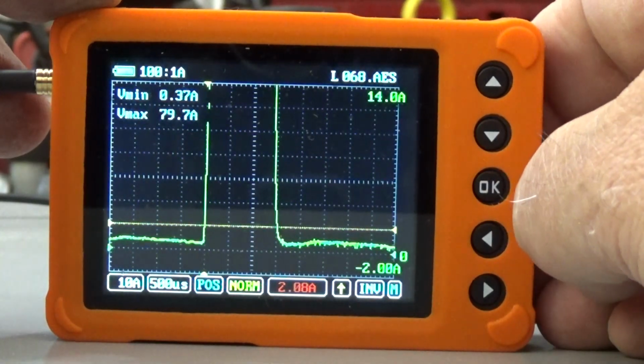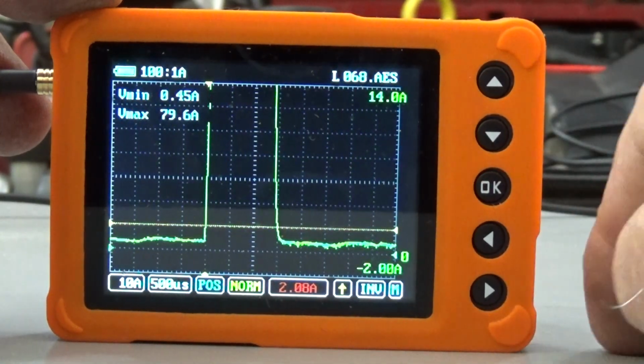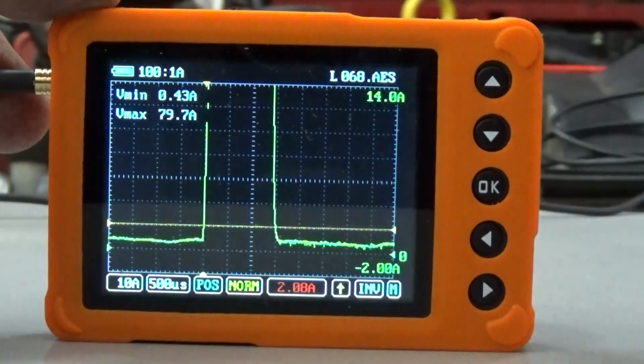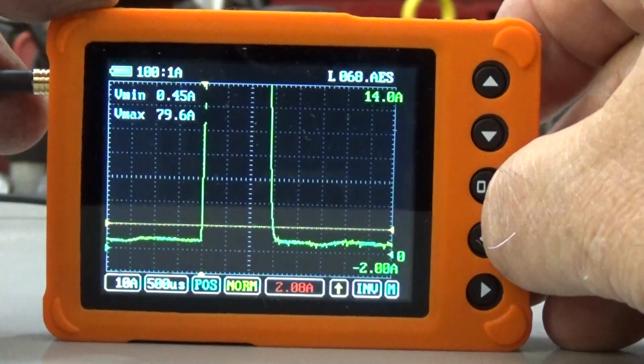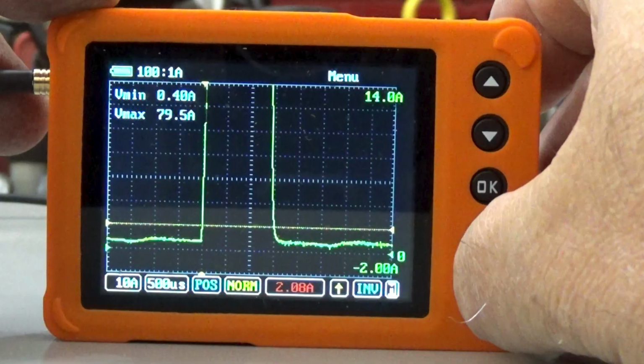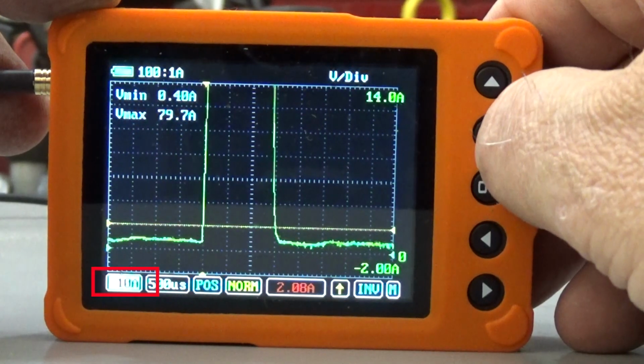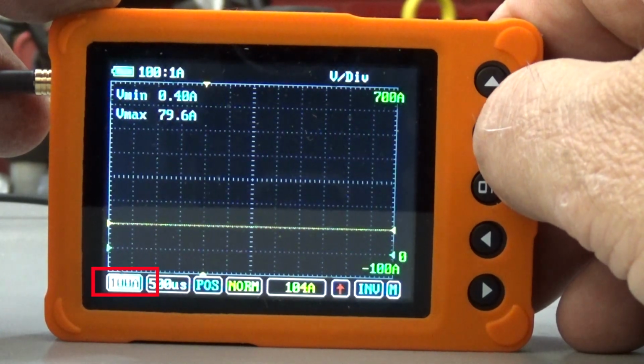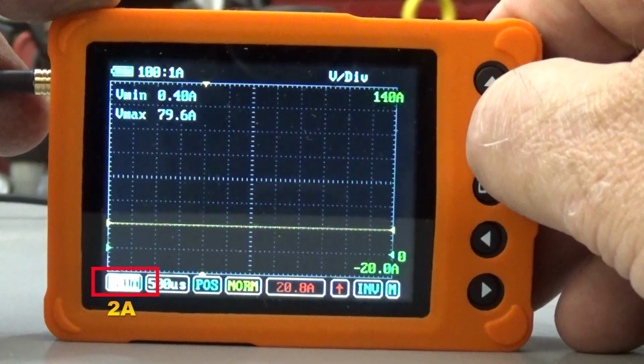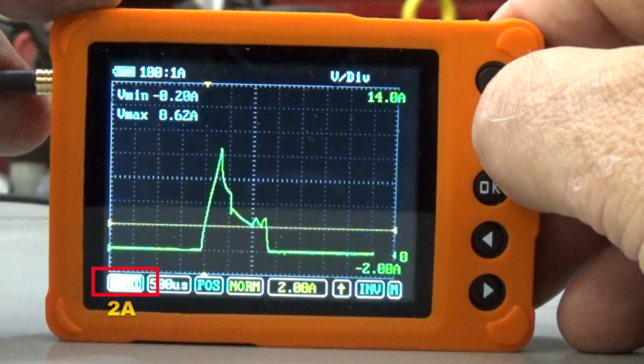The first thing you should notice is a glitch that AES Wave is working on a fix for. Check the amp scale and notice that it says 10 amps, not the 2 amps you set it on. However, the horizontal scale still reflects a 2 amp scale, and yet the maximum value on the meter is 79.5 amps, which is not correct. You'll need to navigate back to the vertical amplitude or amp scale and set it back to 2 amps to correct the waveform on the screen.